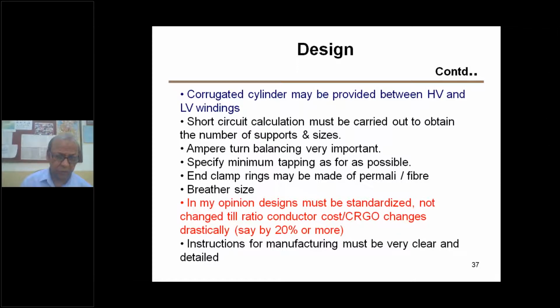Specify minimum tapping as far as possible. You should not use tappings as a liberty, specifying any tapping you like, any plus or minus range. Whenever a tapping is there, it is a cause of poor reliability. So you specify whatever the tapping really requires. So minimum tapping should be specified. And the clamp ring may be made of permali fiber, that you can do.